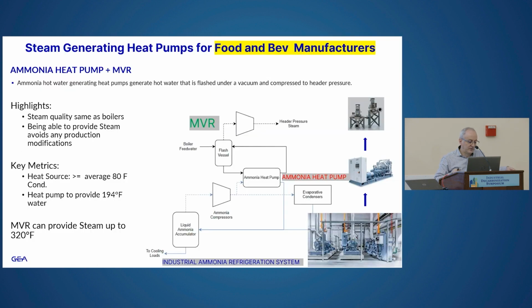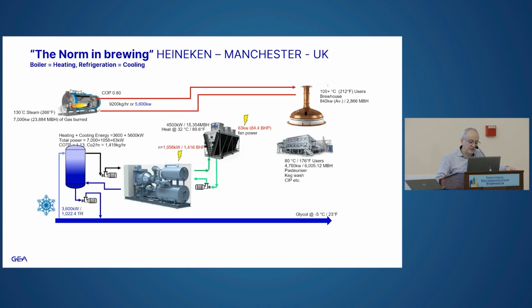In many opportunities, you take the heat source you have today, like food and beverage refrigeration systems, put in a heat pump to make hot water, and send water from the heat pump to an MVR. Basically, this is a flash vessel under vacuum. Water flashes from water to steam because it's under vacuum, or negative pressure, and now you make steam. This is Heineken Manchester in the UK, where the refrigeration system serves the glycol, or cooling, side, and that heat was being wasted through condensers. Then you have the boiler making steam for fermentation, and steam making hot water for the keg wash, pasteurizers, and cleaning in place.